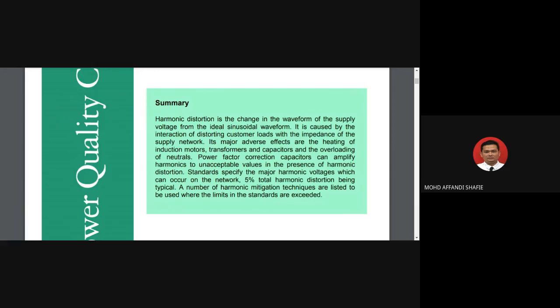Harmonic distortion is the change in the waveform of the supply voltage from the ideal sinusoidal waveform. Normally in an AC source we have the ideal sinusoidal waveform. But when harmonic distortion occurs in the electric supply system, our waveform becomes non-sinusoidal. Harmonic distortion makes the original supply waveform non-sinusoidal. It can be caused by the interaction of distorting customer load with the impedance of the supply network.